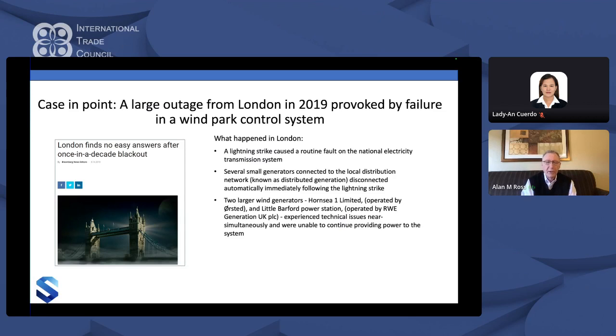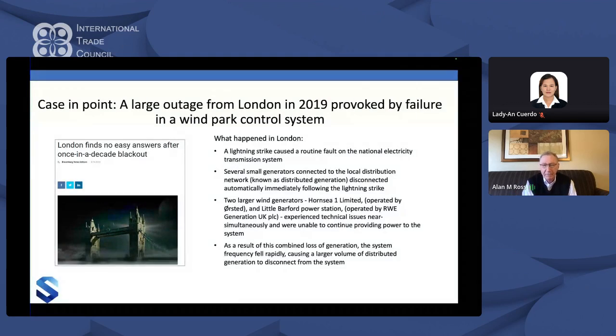So now you've got this rippling effect. Two of the larger wind generators, also had technical issues because of the near-simultaneous problems happening. So they go out too. One lightning strike causes one problem that could be routed around, but several small generators on the local distribution go out, and then two larger wind generators go out. And remember, they're generating power - all of this caused the system to drop frequency. It fell rapidly, and all of a sudden a large part of London goes out.